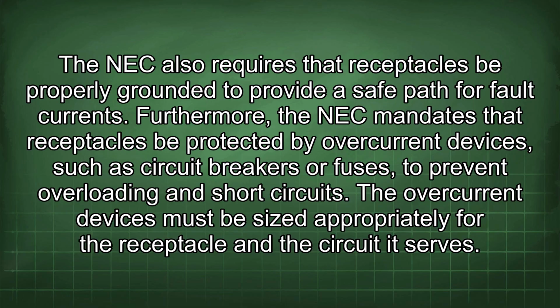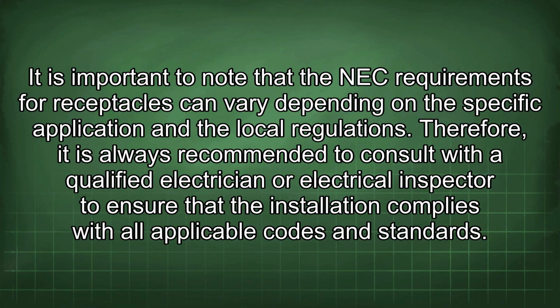Furthermore, the NEC mandates that receptacles be protected by overcurrent devices, such as circuit breakers or fuses, to prevent overloading and short circuits. The overcurrent devices must be sized appropriately for the receptacle and the circuit it serves. It is important to note that the NEC requirements for receptacles can vary depending on the specific application and the local regulations. Therefore, it is always recommended to consult with a qualified electrician or electrical inspector to ensure that the installation complies with all applicable codes and standards.